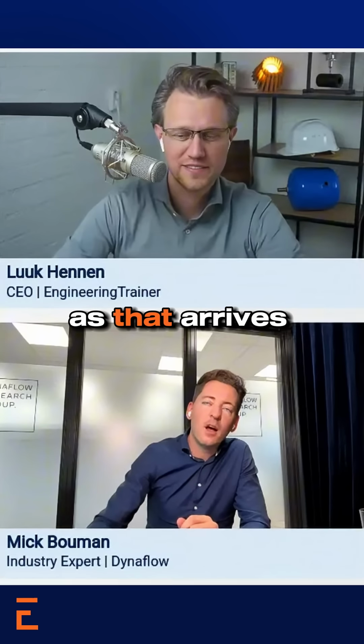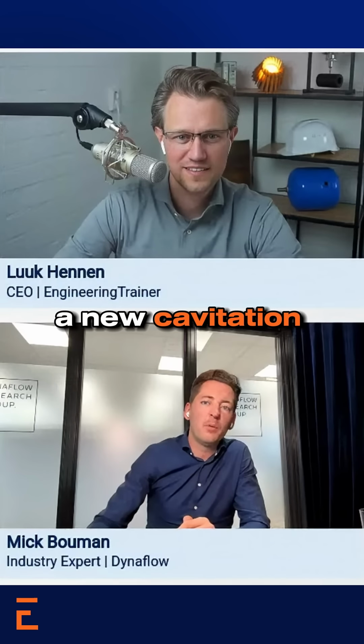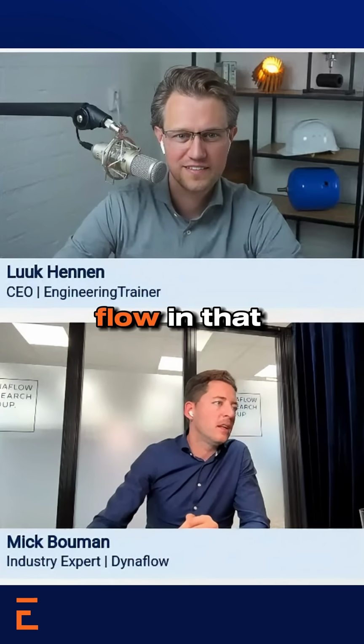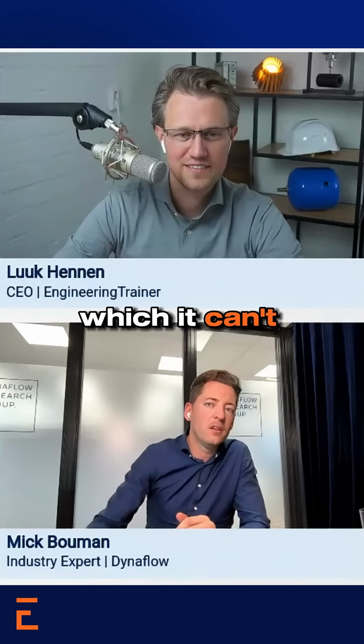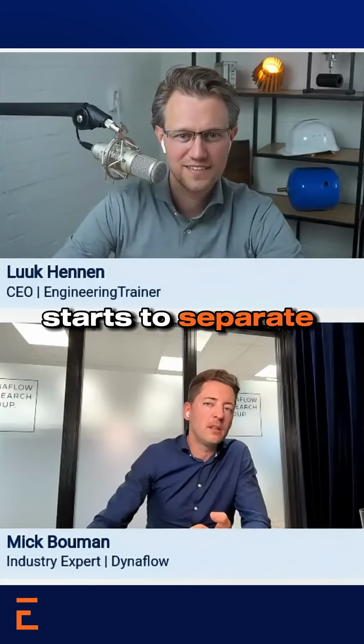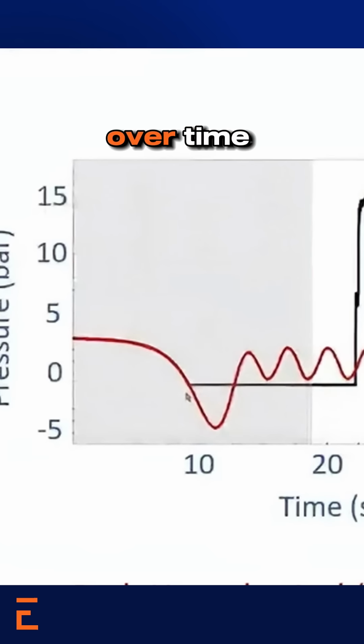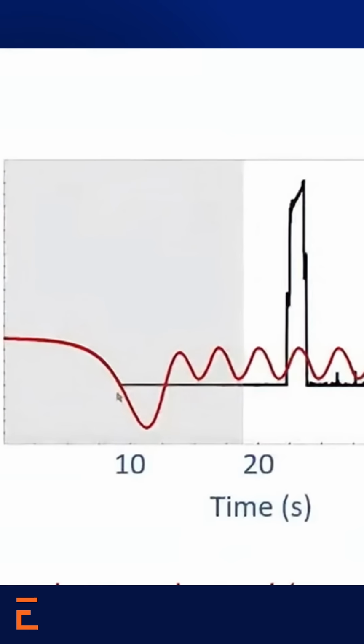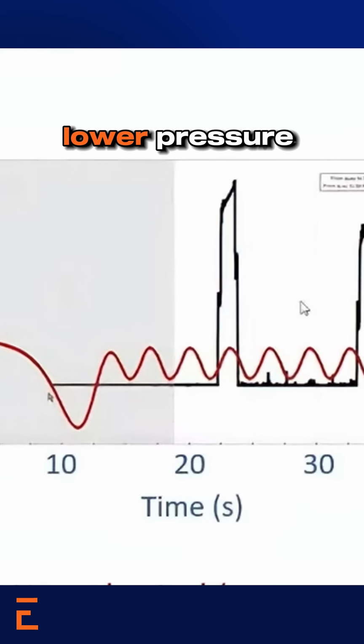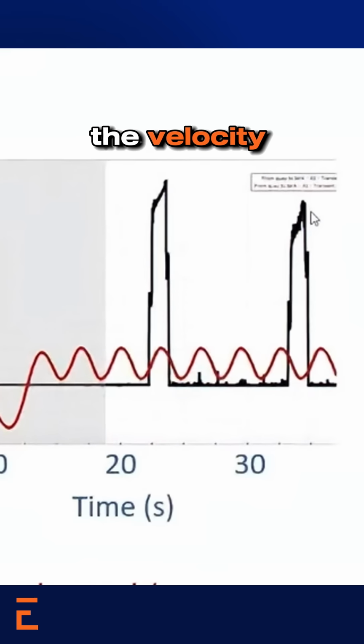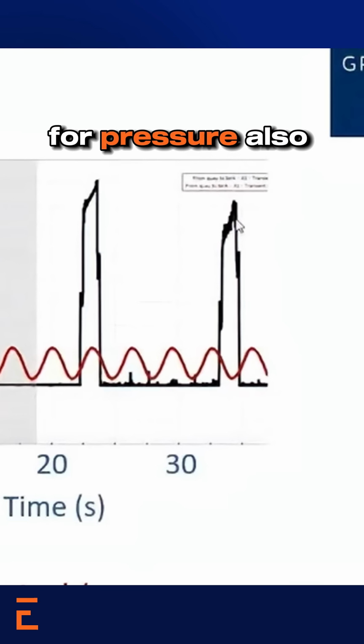And as soon as that arrives at this location, you will have a new cavitation bubble because you have a flow in that direction, which it can't. So at the high point, it starts to separate again. And that process keeps on repeating. And pressure drop over time makes these things shorter together in time and also lower pressure peaks, just because the velocity is removed and the potential for pressure also reduces with that.